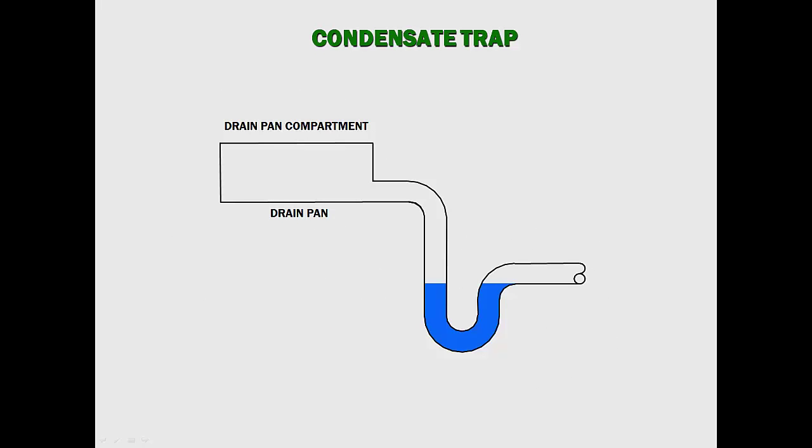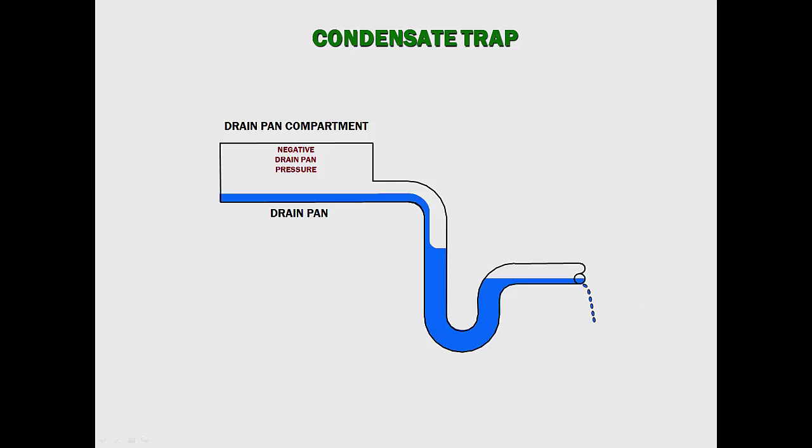When the air conditioning system is not operating, the trap must retain enough water to affect a seal when operation begins. When the air conditioning unit starts, the trap water rises, negates the negative pressure, and prevents airflow into the drain pan. As condensate flows, the trap is filled, and the water column rises to a level necessary for condensate to flow from the trap.